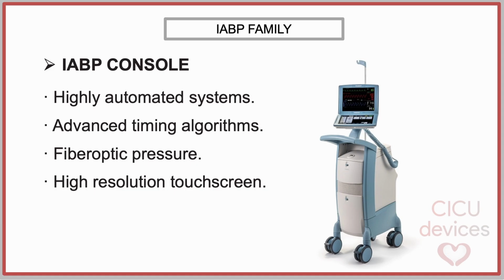Modern IABP consoles are compact, portable platforms designed for use in intensive care units, catheterization laboratories, operating rooms, and during inter-hospital transport. Current consoles incorporate advanced automatic timing algorithms capable of synchronizing balloon inflation and deflation using either the electrocardiogram or the arterial pressure waveform. The latest generation consoles also support fiber-optic arterial pressure sensing through compatible balloon catheters, enabling direct, high-fidelity aortic pressure monitoring and further improving timing accuracy.